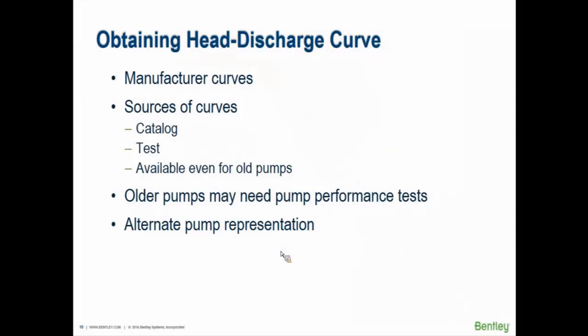You might go to a manufacturer catalog, but for an older pump you may need pump performance tests to determine if the pump curves are actually producing the flows you believe. For example, a 20-year-old pump with a curve from its original installation is likely not operating at that original curve anymore. Using the true pump curve through pump testing would be calibrating your model to predict the real world more accurately.